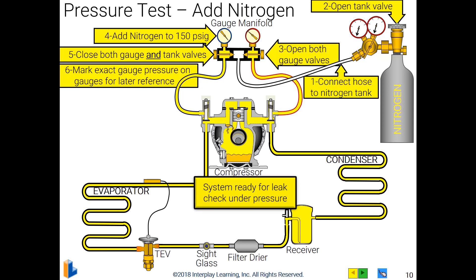Now it's time to go to lunch. Whenever I'm doing an install, I try to get it up to this point by lunchtime. I go to lunch, come back, and look for 150 PSIG on my gauges. If it's still there at 150, I'm good to go. If it's not, it's time to look for a leak. So let's take a break and I'll see you on the next one.